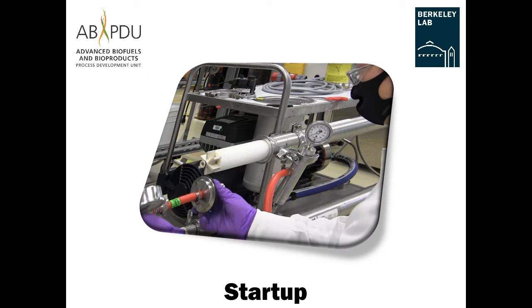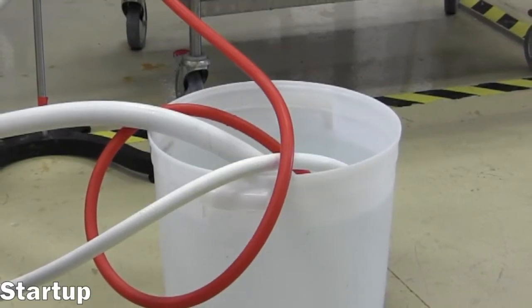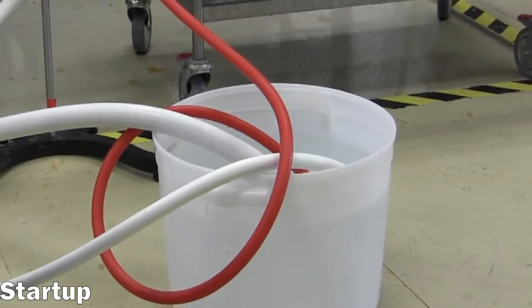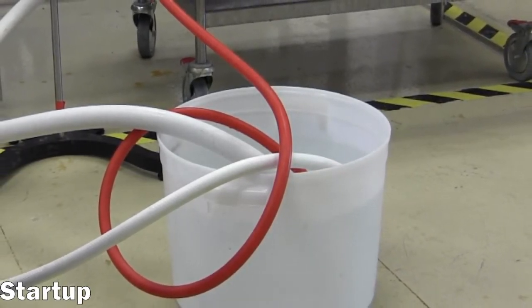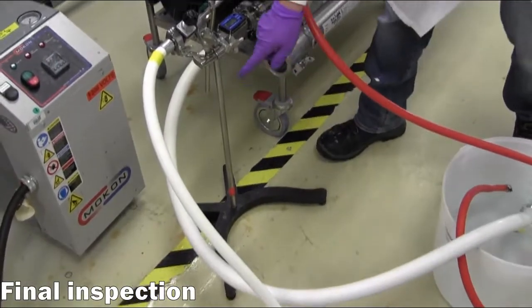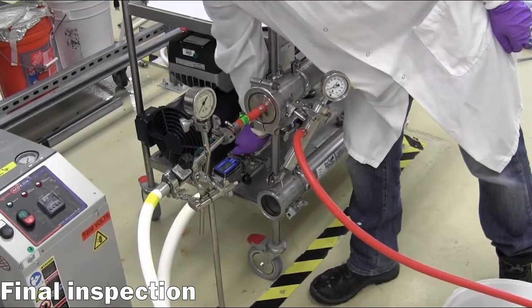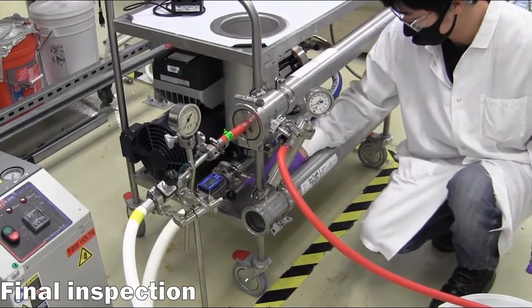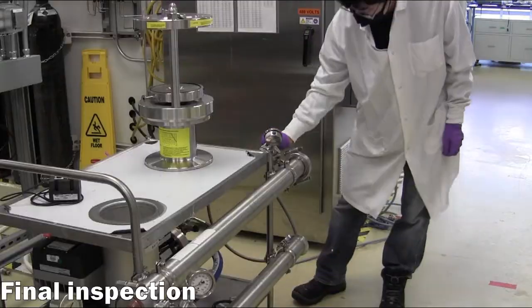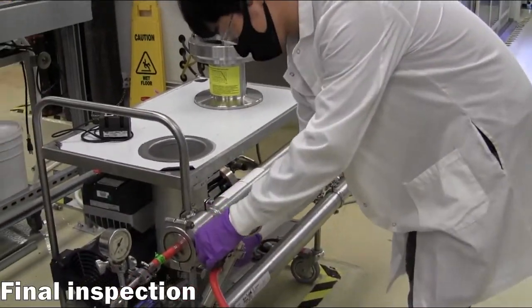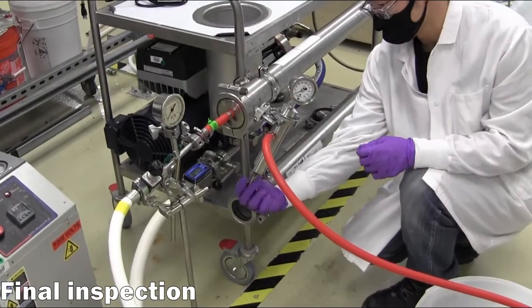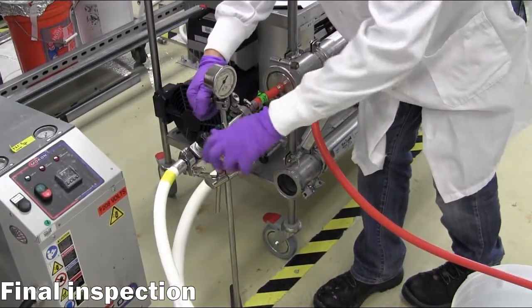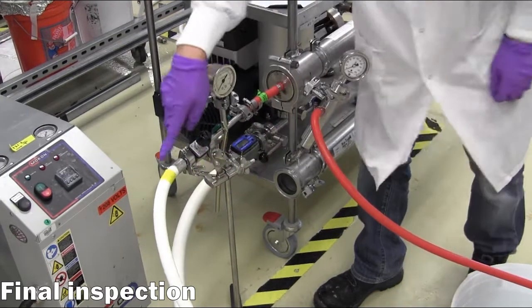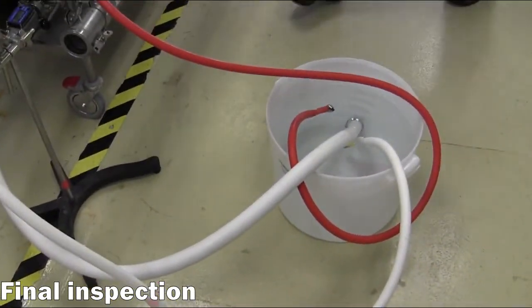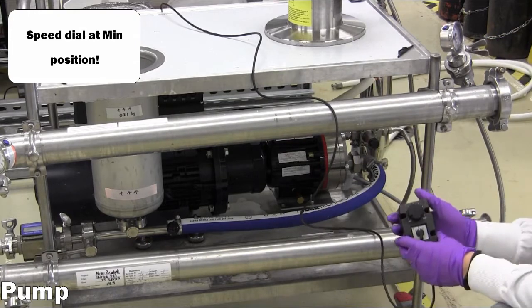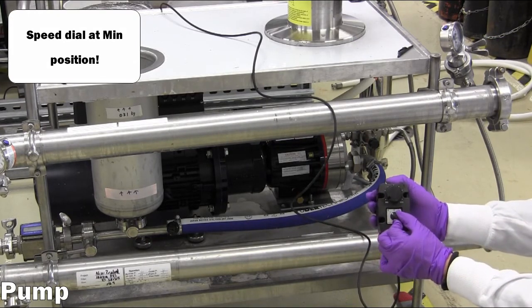Startup. The operation begins with all the inlet and outlet hoses placed in the water bucket to recirculate while the system primes. Ensure all valves are open, clamps are secure, and there is no back pressure applied on the retentate outlet manifold. The pump is then switched to the on position, and water will begin circulating and priming the membrane.